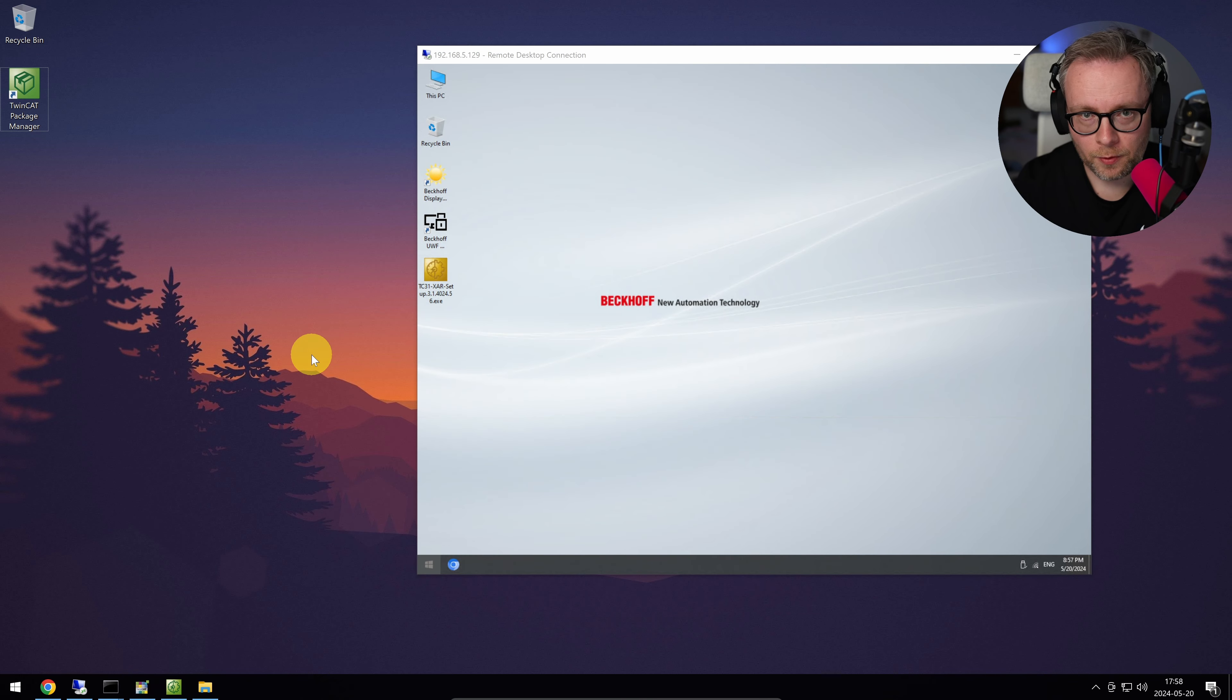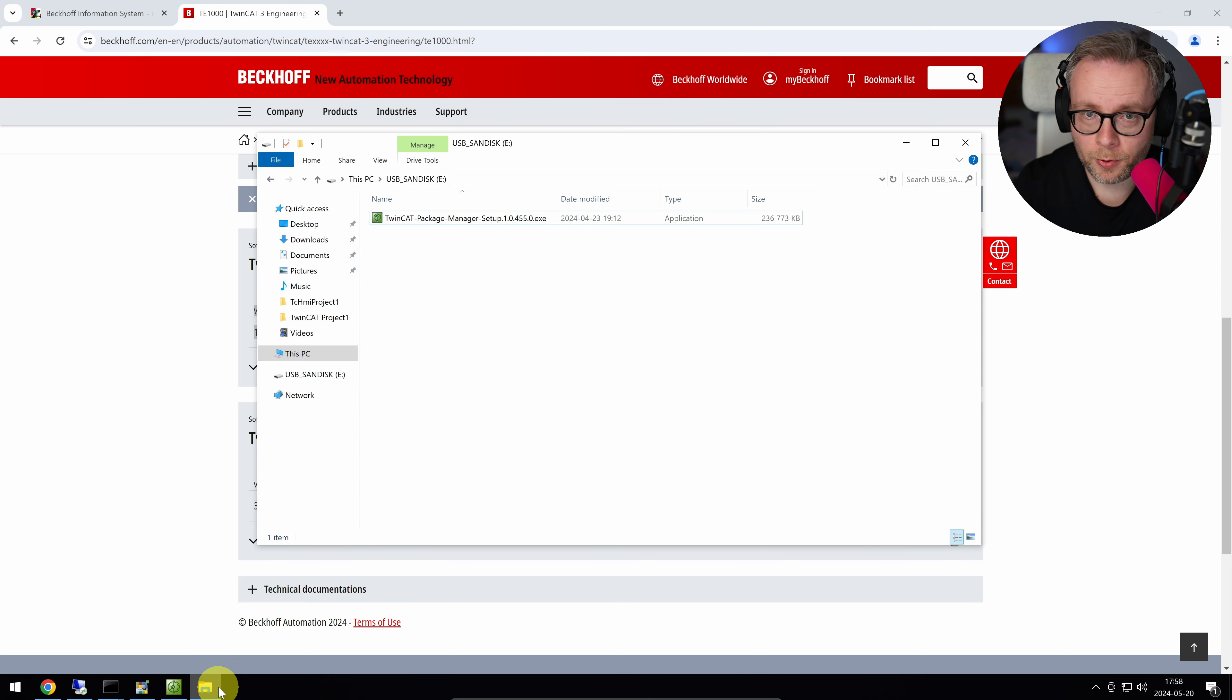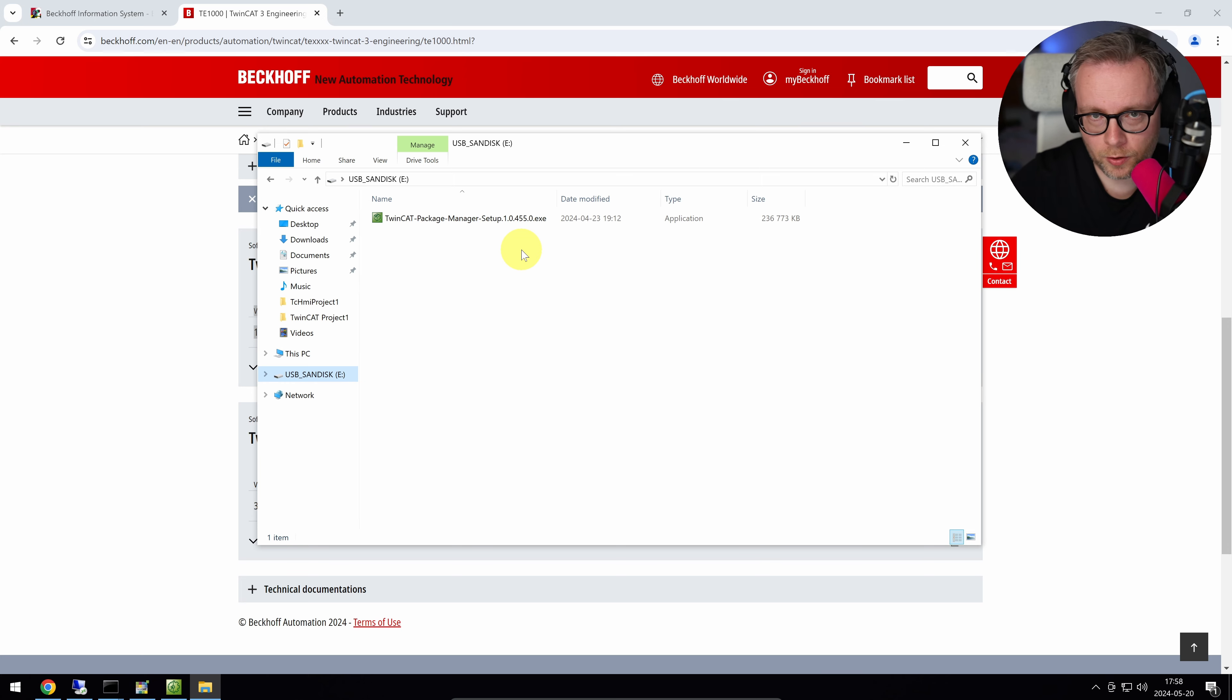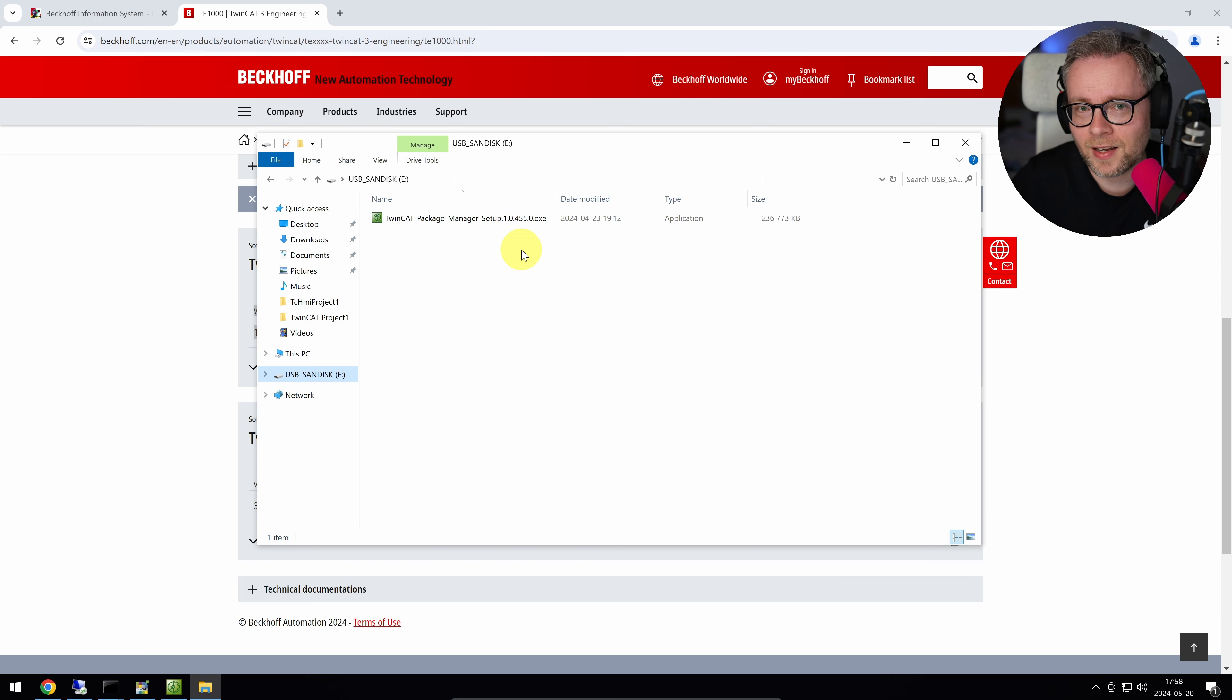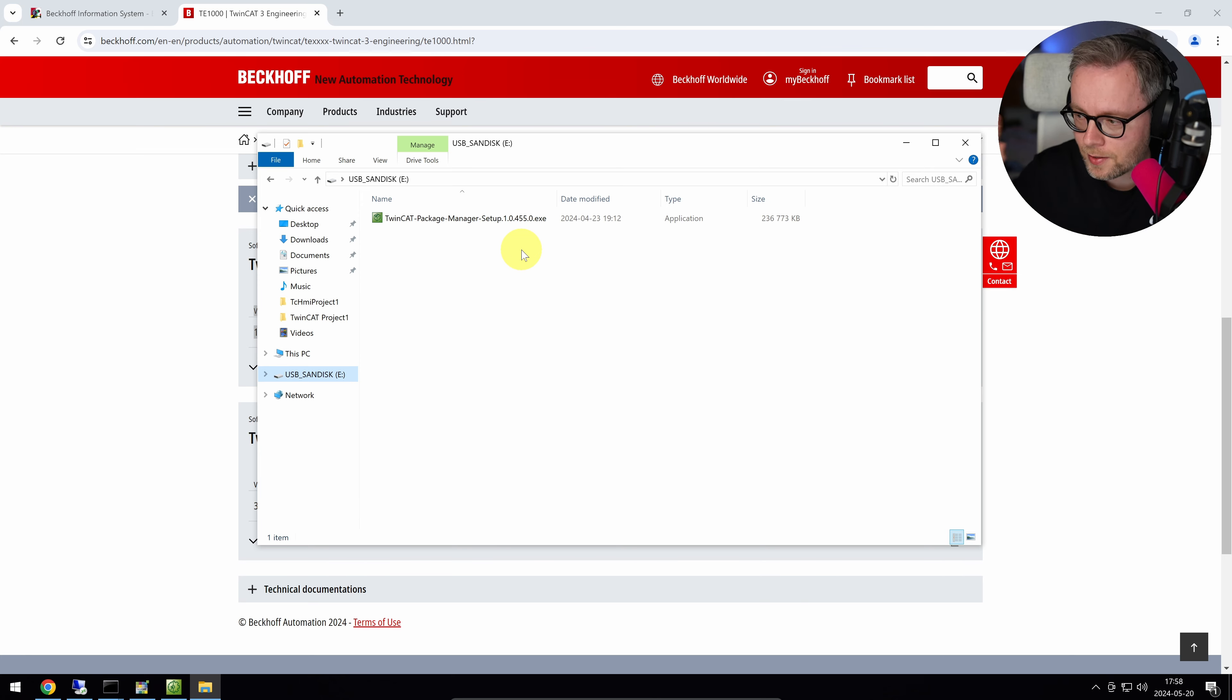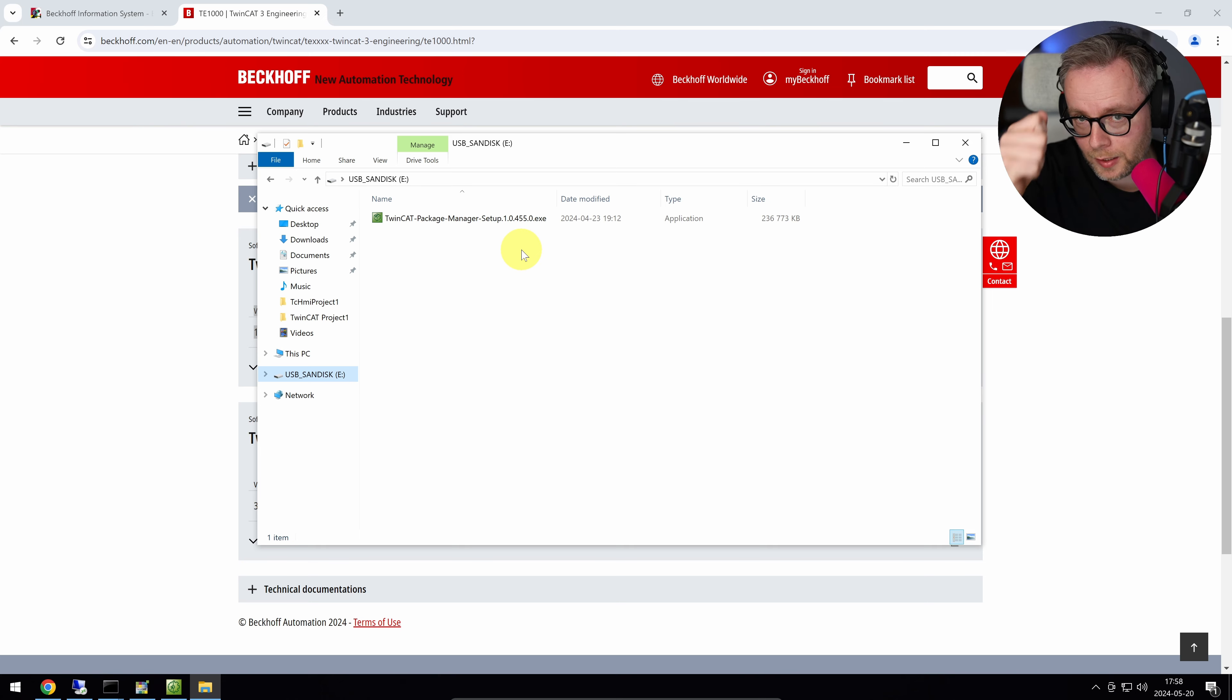The first thing you're going to have to do is to download the package manager itself. And this is available through the Beckhoff website. So I simply downloaded the package manager and I put it on a USB stick. So you're going to have to put it on a USB stick because we're going to transfer it to the PLC. Of course, if you have network connection to the PLC, you could just download it directly. But here I'm assuming the common case. And that is that the PLC has no internet connectivity. It might have connectivity locally in our network, but there's no internet connectivity to it directly. It's a standalone unit standing in some dirty old factory somewhere, and we're going to install TwinCAT 4026 on it.